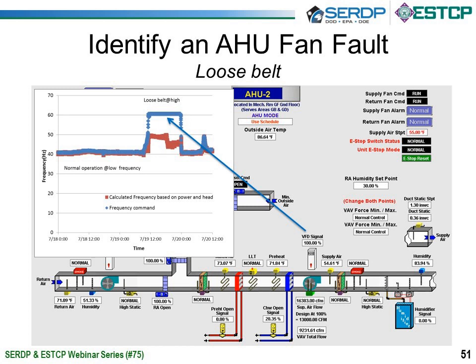As you can see, up to about 11 a.m. on 7/19, there's a nice match between the frequency command and the calculated frequency from measured data. As we proceed, there's an increase in the frequency command requesting a higher flow rate of air. The red line does not keep up with the request. This is an indication that the belt is slipping. The velocity of the fan is lower than the velocity being requested, and therefore is an indicator of a loose belt or slipping belt.